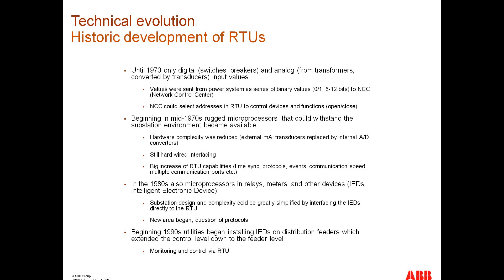In the beginning of the 1990s, utilities began to install IEDs, the intelligent electronic devices, in the distribution feeders. This, at the end, and this is state of the art, extended control down to the feeder level. So it is now possible to have control from the RTU, or from the NCC, down to the feeder level, and the RTU has the functionality to both monitor and control.